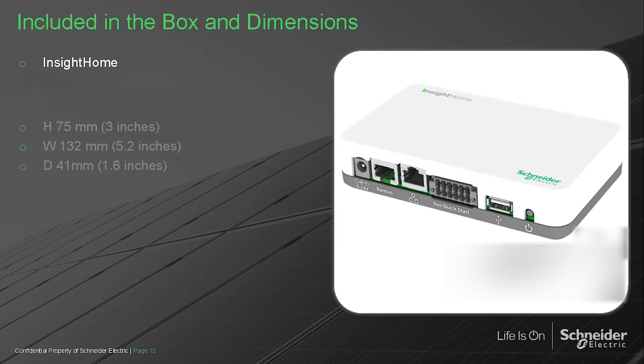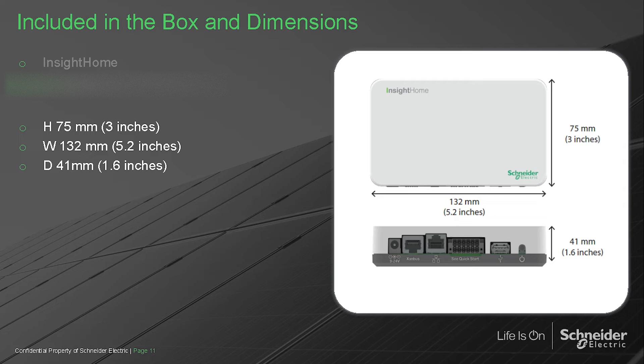For those familiar with the gateway, you'll notice right away there's a single Xanbus port and an Ethernet port for hardwiring to the router. You have your 12-pin connector, which we'll talk about, a USB port, and an on-off switch. InsightHome is very small, about the same length and width as an iPhone but a little thicker, so a very small, lightweight device. You have a power button that can turn the unit on or off, and it can also be held down to reset to different levels, including factory defaults.